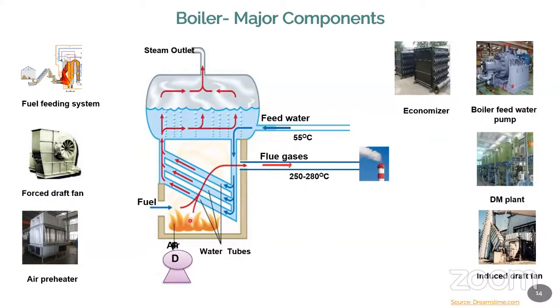Suppose your air is not sufficient, what will happen? That's another important question. If the air is higher, what will happen? The heat produced by the fuel is taken away by the flue gas, correct? But when the air is not sufficient, what will happen? Then automatically oxygen is not sufficient. So the combustion will not take place. That means the combustion is not 100%, it is partial combustion.